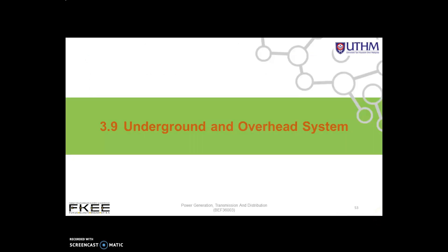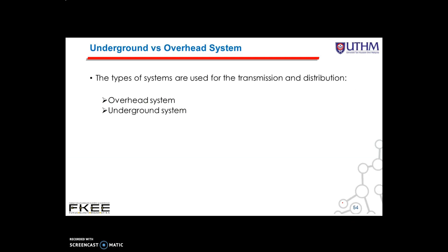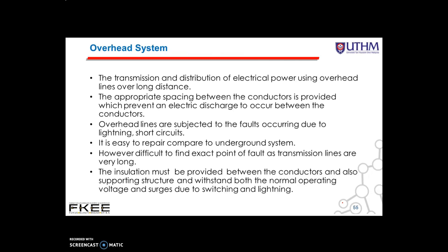Next is underground and overhead systems. The distribution system can be overhead or underground. Overhead lines are generally mounted on wooden, concrete, or steel poles which are arranged to carry distribution transformers in addition to conductors. For the underground system, it normally uses conduits, cables, and manholes under the surface of the street and sidewalks. The transmission and distribution of electrical power using overhead lines covers long distances, and appropriate spacing between conductors is provided to prevent electric discharge between them.